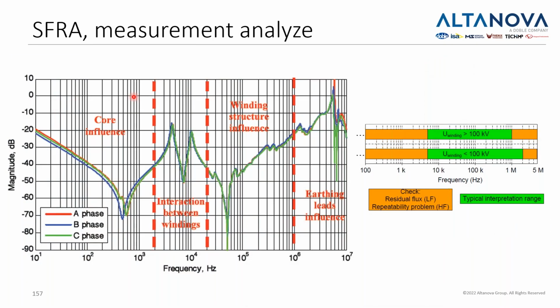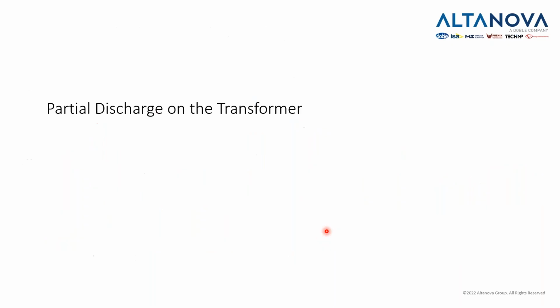But what I wanted to tell you is that this graph itself doesn't tell you anything, but when you compare it with the old results, you will see the influence of the core, which is the first part, then interaction between windings, then winding structure influence, and then earthing leads influence. So if everything is okay, let's say here, and something is not okay here, then you know that there is a problem with earthing leads influence.